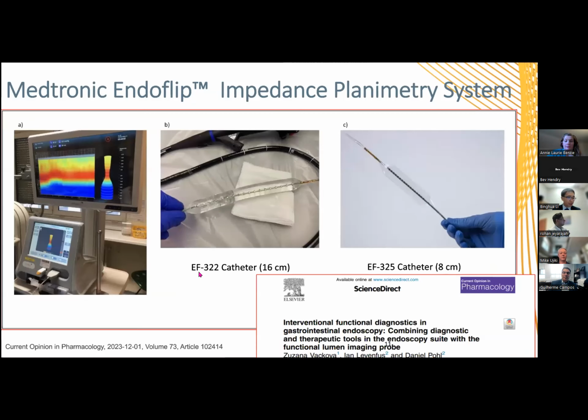Here is the most commonly used FLIP system, the EndoFLIP. I think everyone probably already uses this. The probe consists of a 24 centimeter by 3 millimeter catheter with a highly compliant bag, a balloon, attached to the tip, surrounded with 16 pairs of impedance electrodes mounted on the catheter, and then there's a solid state pressure transducer on the distal end of the catheter.